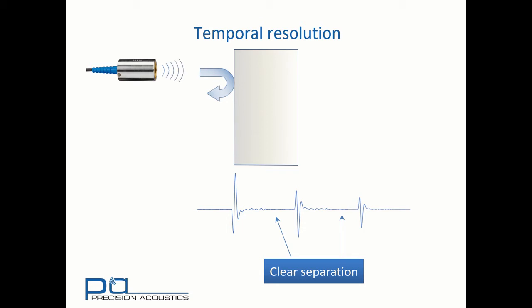This is very useful if we're in a thickness gauging application, or if we're using the amplitude of reflected pulses to determine an image from within the sample, as we might find in diagnostic medical ultrasound. Short pulses are excellent for maintaining the ability to resolve small spatial features within the sample that we're looking at.